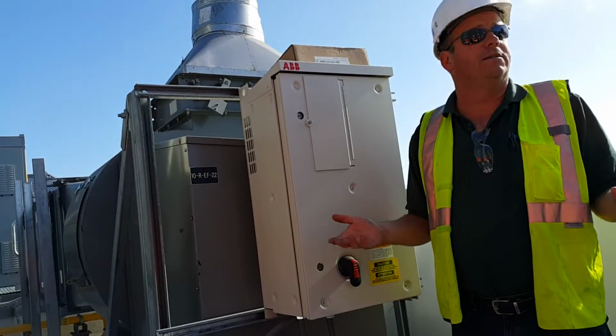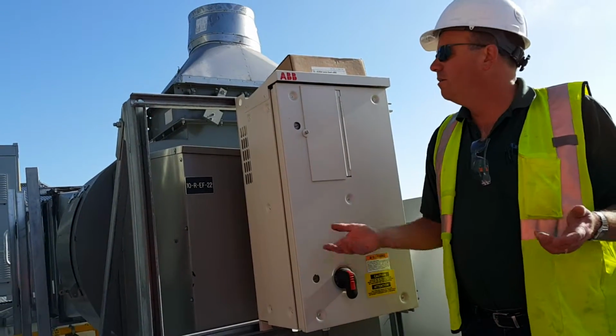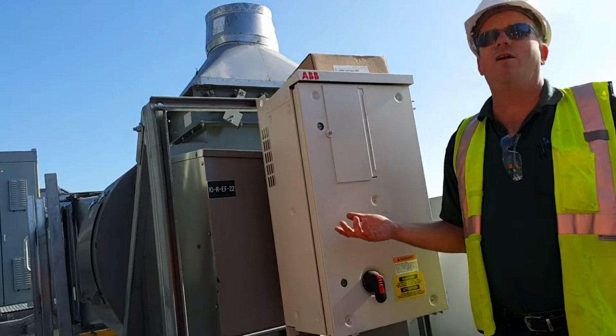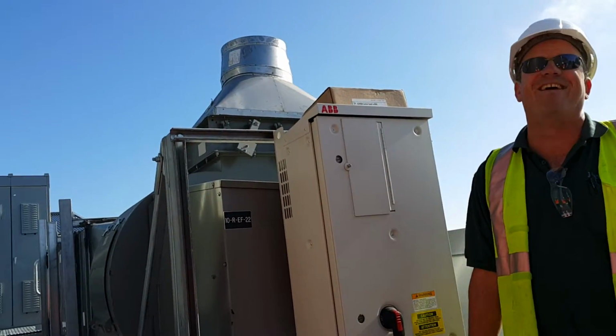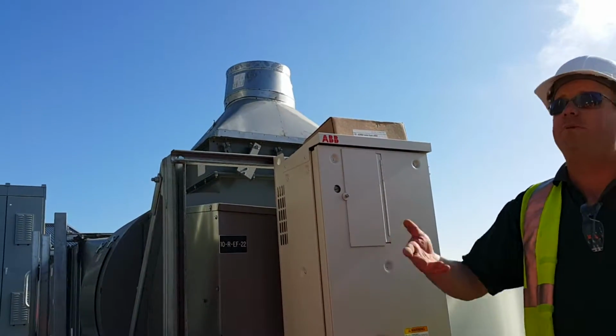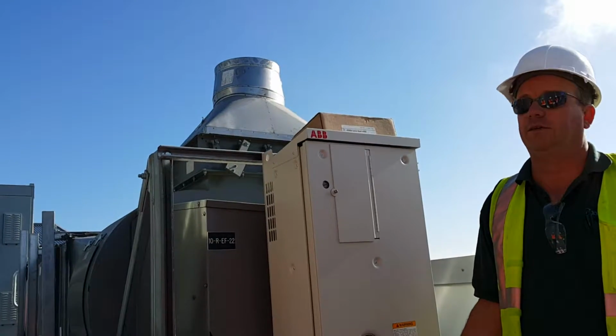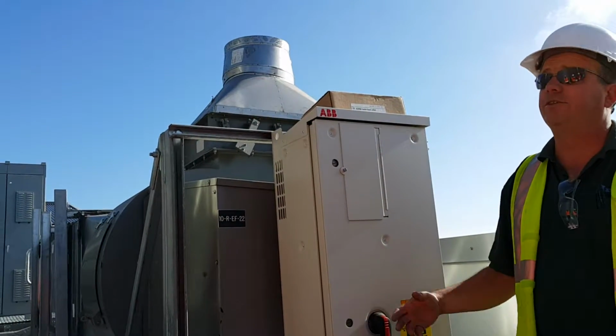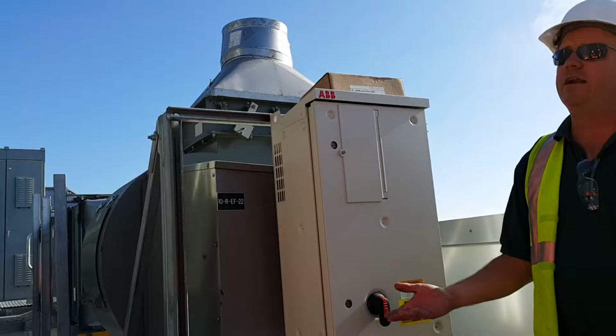Okay, it was a ground fault basically. It means a ground fault in the motor. But that was 5 years ago. They go, oh yeah, that's when we changed the motor. Yeah, the motor went bad. And meanwhile, it was the BMS system shutting it down for whatever reason, or a safety circuit, you know, an overpressure, anything like that. Yeah. You know, shut it down.